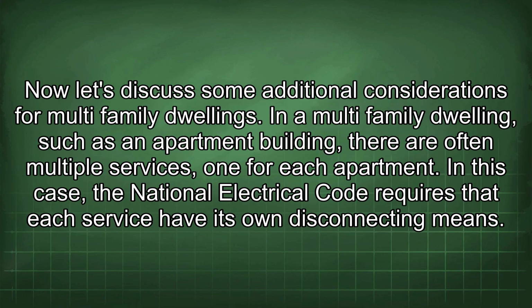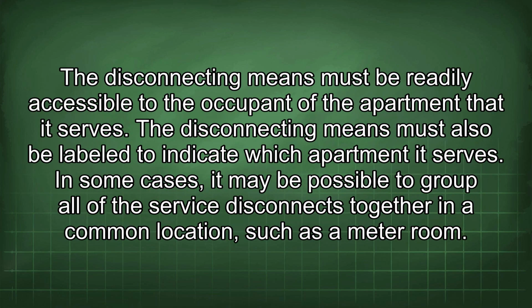Now let's discuss some additional considerations for multi-family dwellings. In a multi-family dwelling, such as an apartment building, there are often multiple services, one for each apartment. In this case, the National Electrical Code requires that each service have its own disconnecting means. The disconnecting means must be readily accessible to the occupant of the apartment that it serves. The disconnecting means must also be labeled to indicate which apartment it serves.